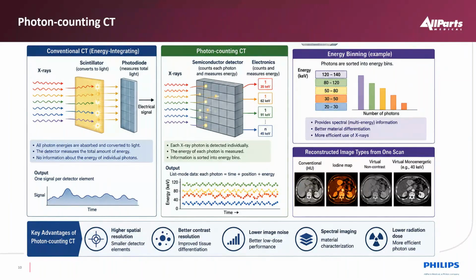Okay. So with regards to photon counting, now we have a binning process where not only do the X-rays come through, but we can tell how many of these photons came through at which energy levels. That gives us a better view, multiple colors so to speak, of the interactions with the attenuation coefficient coming through the patient. So you see all the way to the far right, the energy binning example given here, and the number of photons. And then in the image, you have a conventional Hounsfield unit image, where we look at the CT numbers, or Hounsfield units, basically an iodine enhancement when the iodine is introduced, and then contrast versus non-contrast multi-energy images.